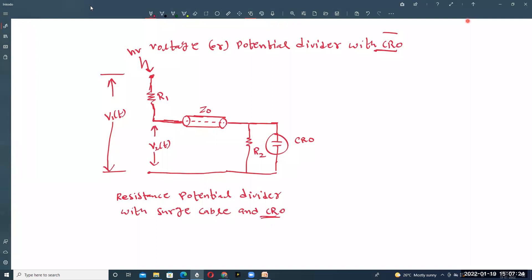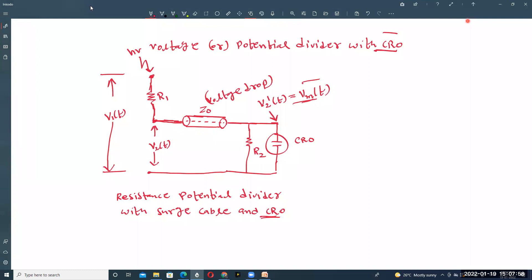V2(t) is the voltage at the junction. The surge impedance of the cable is present here, and the voltage measured by the CRO is called V2'(t), which is the meter voltage Vm(t). V2'(t) is not equal to V2(t) because there is a voltage drop in the surge cable, so the actual voltage at the junction differs from what the CRO measures.